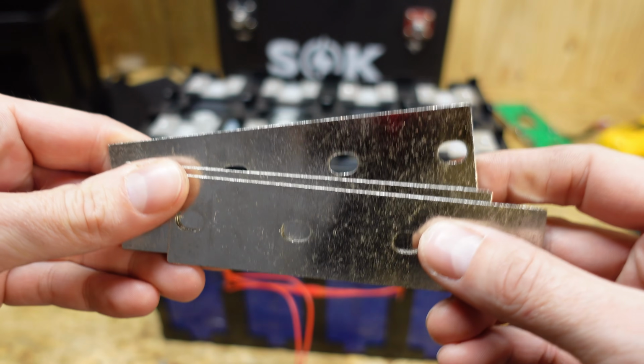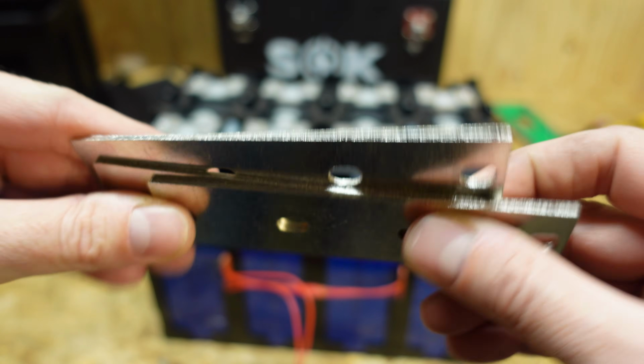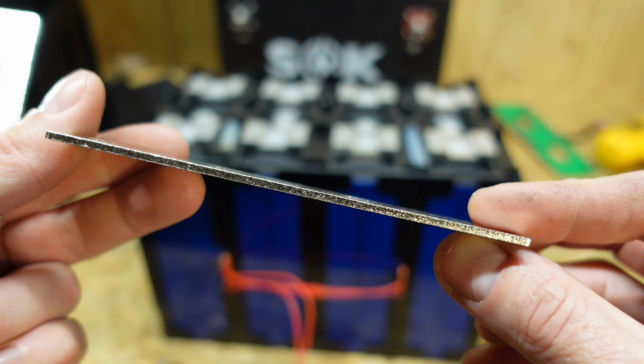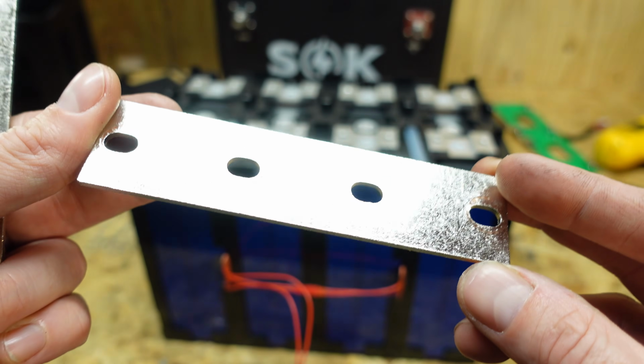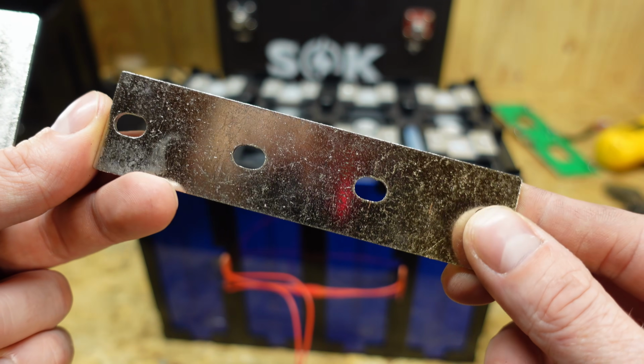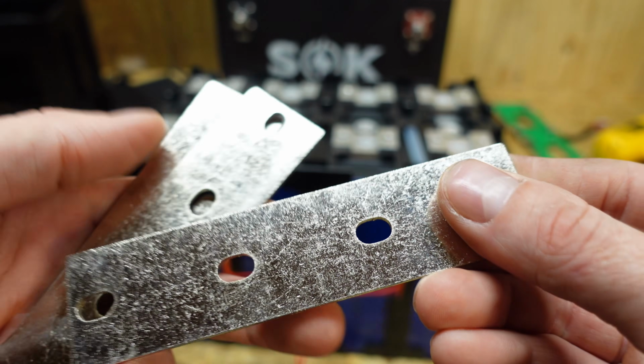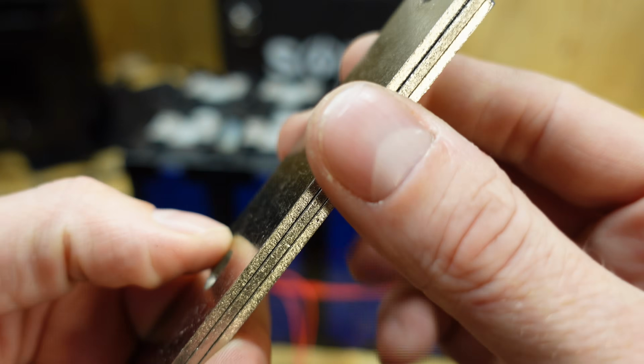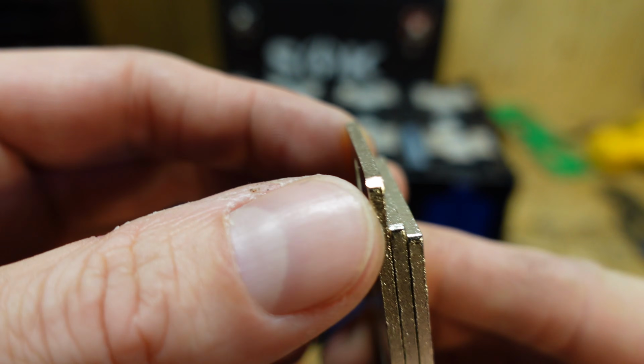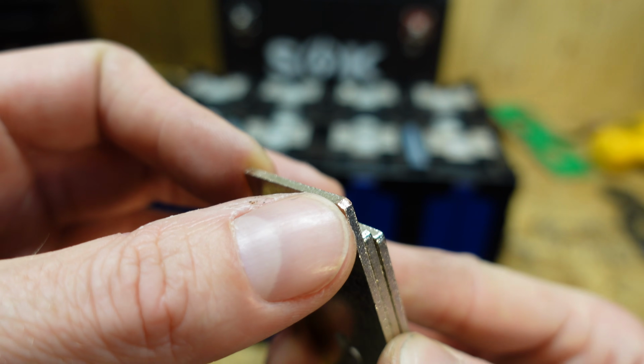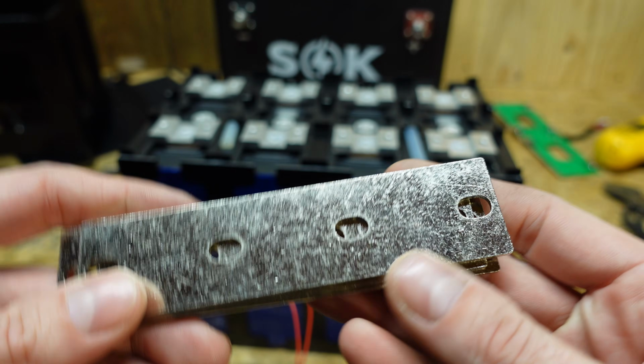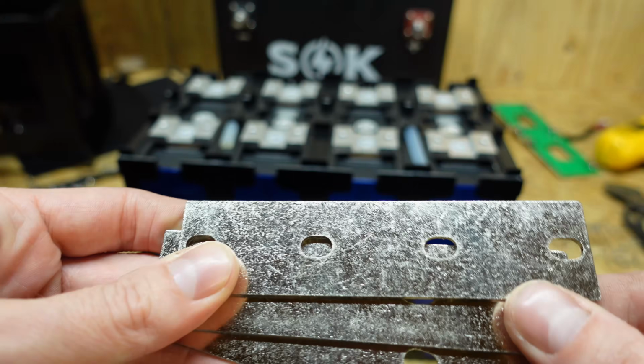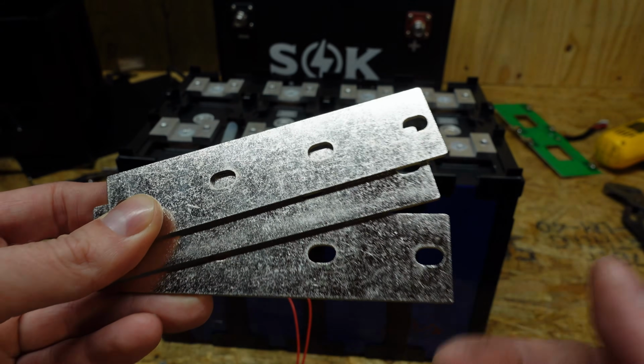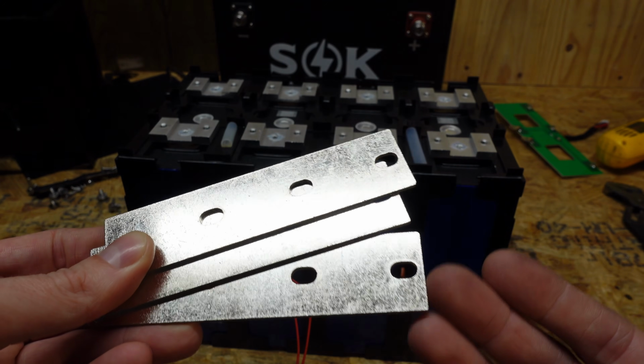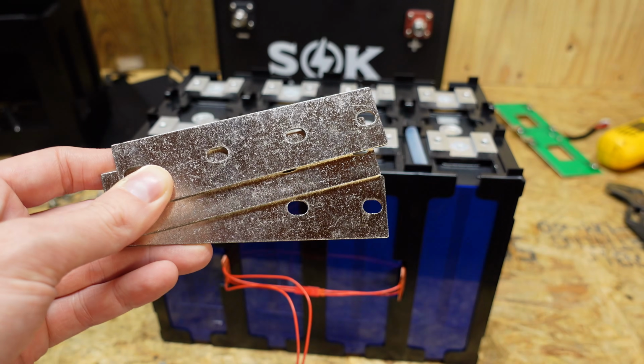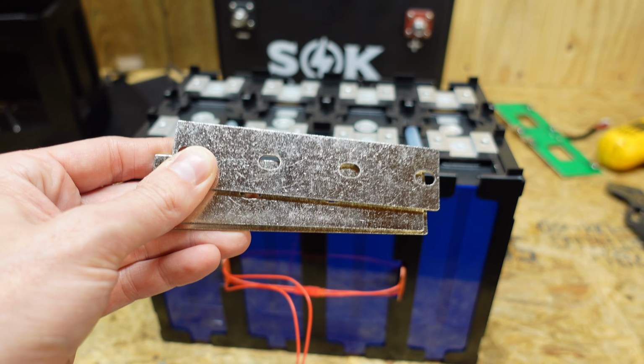These are the bus bars used on these cells. They are rigid pieces of metal with a fair amount of mass to them. I think 200 amps is probably where I'd stop, which is the rating of this battery. They are not aluminum. I did file the corner of this one back here, I don't know if you can see it, but it does have a very slight copper color. I seem to remember they were using some sort of copper nickel alloy or something, some sort of copper alloy. So they are not aluminum, but they are also not pure copper. But they are pretty good bus bars.